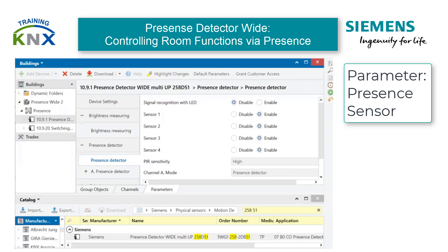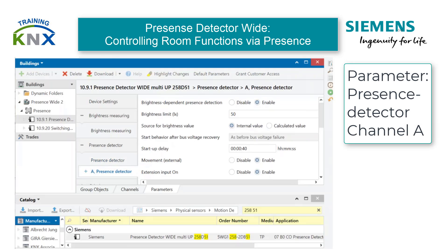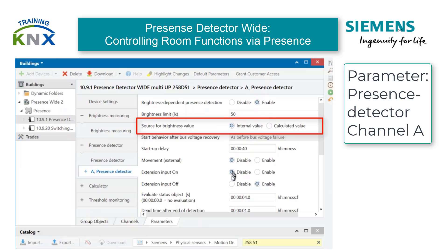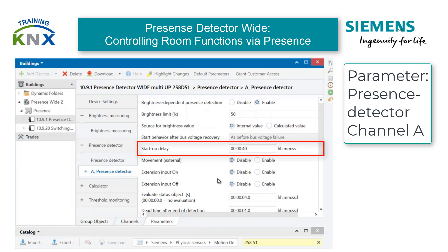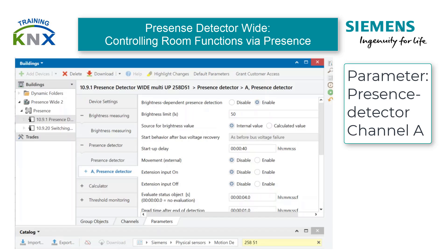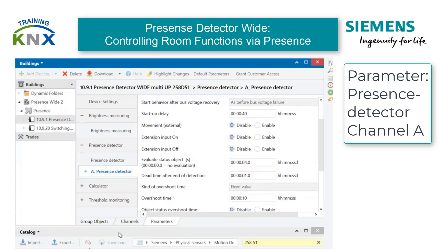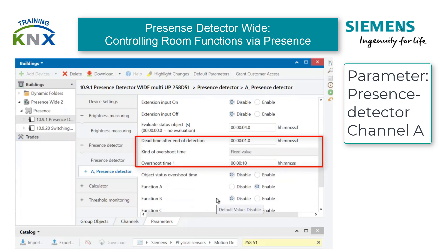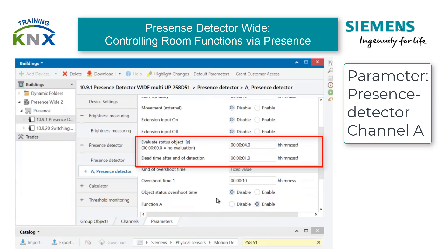Further to channel A Presence Detector. We'll use the default parameters: Brightness Dependent Motion Detection, Brightness Limit 50 lux, Source for Brightness Value internal, Startup Delay 40 seconds. The movement trigger and extension input settings must all be set to disable. If the lamps are not expected to cause any major temperature fluctuations in the detector area, the time parameters for the status feedback object and the dead time after the end of detection can be set to zero.